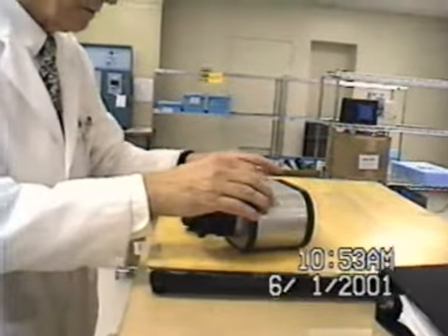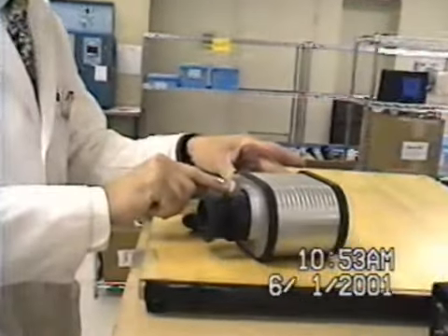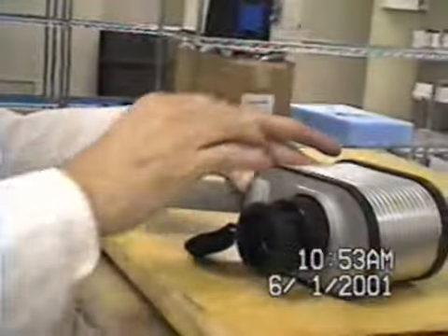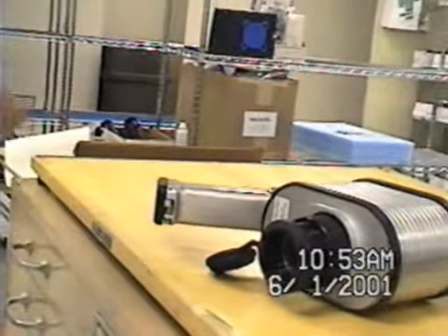Then you tighten. You put in 440 screws, 3/4 inches long, and you put them in evenly. And again, not too much force. If you have too much force, you've got a problem. Just go together, hand tight.